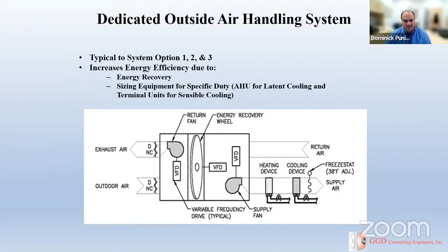Next slide. So this would be in all options, just how we achieve that heating and cooling would be dependent upon the system selected. Next slide. All options, what we're proposing, would also have a building energy management system, a BMS. That would control and monitor the HVAC systems. It will allow for zone scheduling, occupied/unoccupied control, and night setback control for certain areas that are occupied 24/7. It could be integrated with the lighting systems. The goal is to provide increased energy savings, and it could also prompt for preventative maintenance, such as when filters need to be changed or when fans need to be lubricated; it will prompt the user. It will also be web accessible, so these could be managed remotely. Next slide.